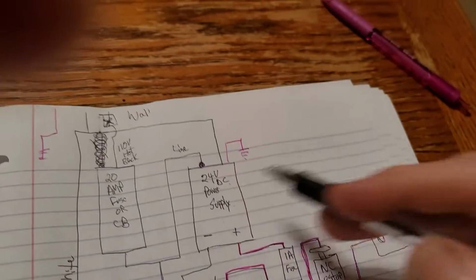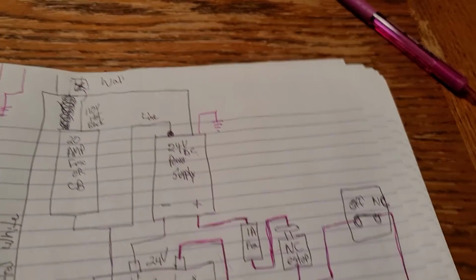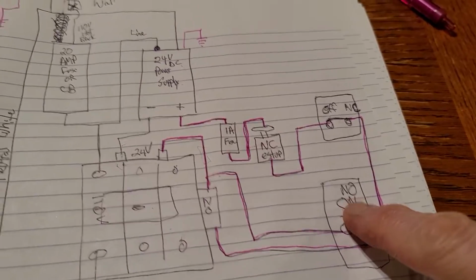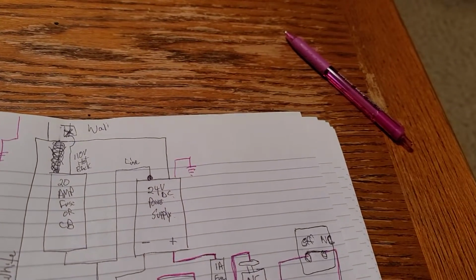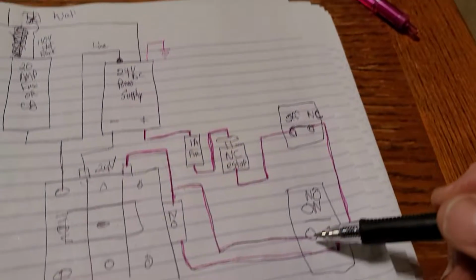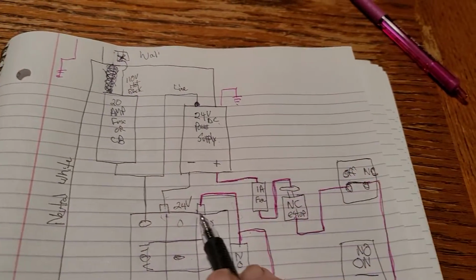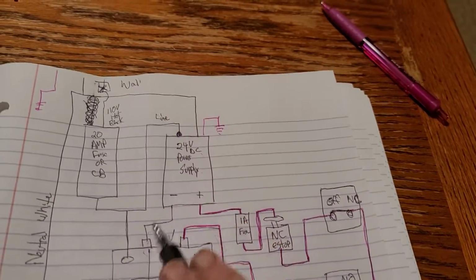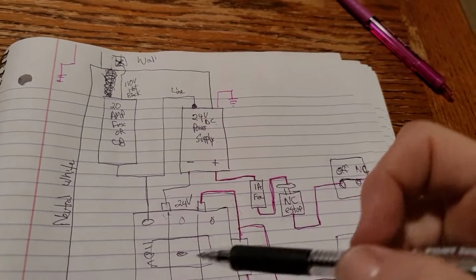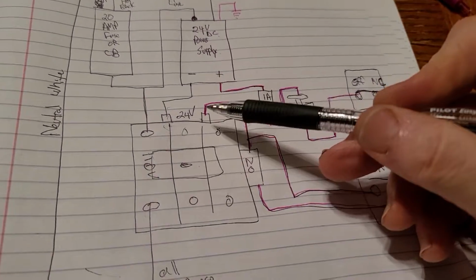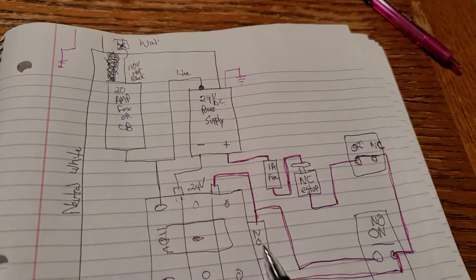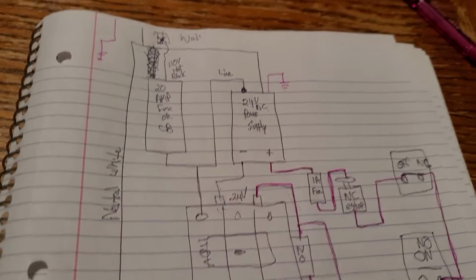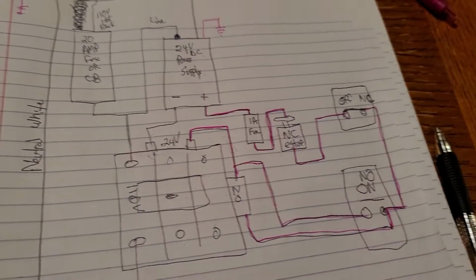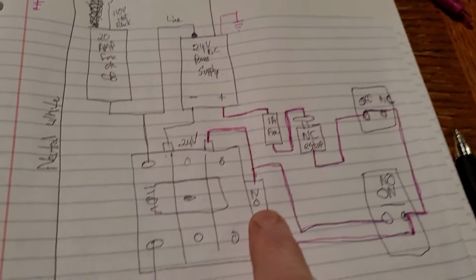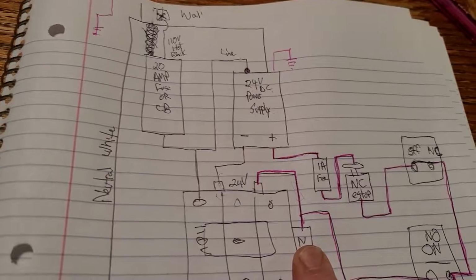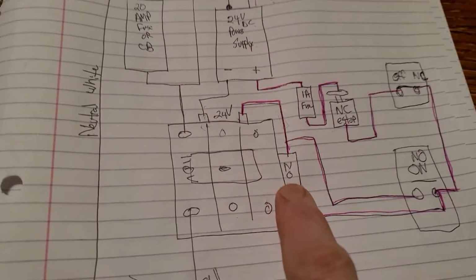So, anyways, remember, voltage is going all the way through until we hit the button. When we hit this on button, we connect it. And what happens is power then flows through this line, through the switch here, and it goes all the way up, and it touches this coil. And when that happens, the coil becomes energized, and power is supplied from the coil through this contactor, and it sucks it in. And when that happens, this normally open right here becomes normally closed, okay? So now, even though we let off of this momentary button, because this is normally open, but power sucked it in, it stays. It's called magnetically latched. This is where the magic happens in the contactor.